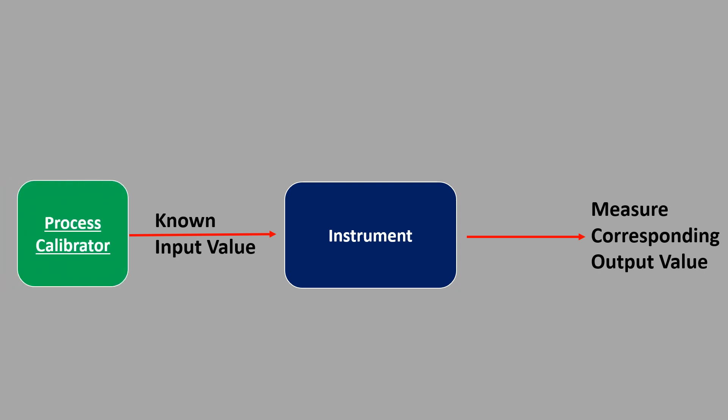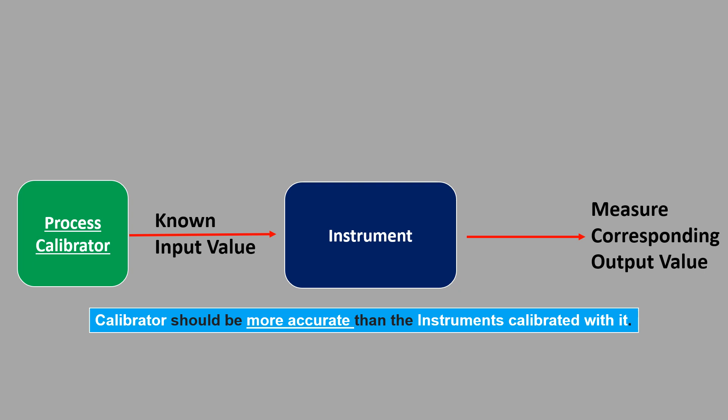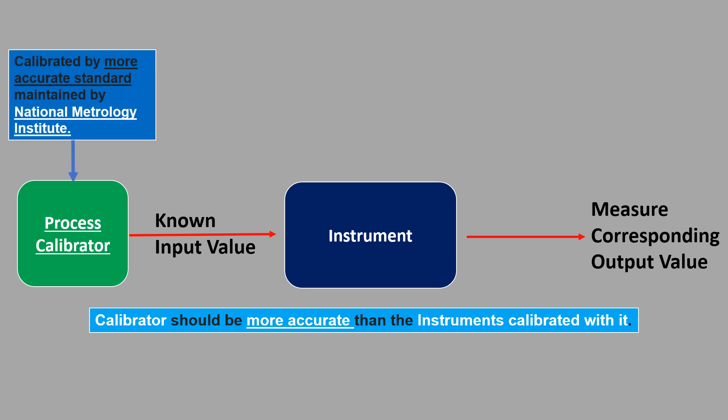Calibrators should be more accurate than the instruments you calibrate with them. Calibrators are calibrated regularly by more accurate reference standards maintained by National Metrology Institutes. After calibrating by more accurate standards, these institutes issue a one-year valid certificate for calibrators.